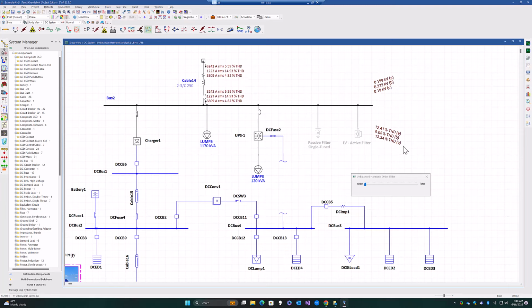And of course, notice what happens also to the voltage total harmonic distortion. So this is why it's important when you are running harmonic analysis in unbalanced systems such as university campuses, buildings, data centers, utility distribution systems, in general, any system where you know you're going to have an unbalanced load, even railway networks for that matter, to switch over to an unbalanced network harmonic analysis to get a better assessment of the situation and size and determine the harmonic mitigation techniques appropriately.